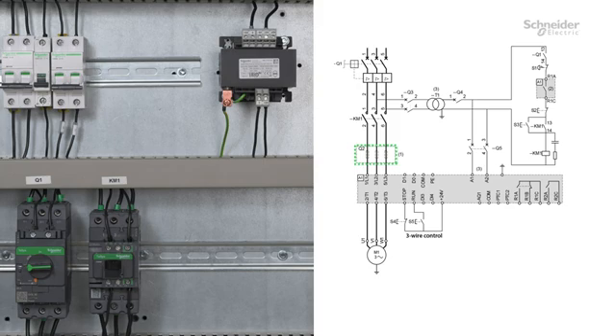Q2 fast acting fuses are to be used only when type 2 coordination according to IEC 60947-4-2 is required. Q3, circuit breaker: protection for the primary of the transformer. Q4, circuit breaker: protection for the secondary of the transformer. Q5, circuit breaker: protection for the control part of the soft starter.